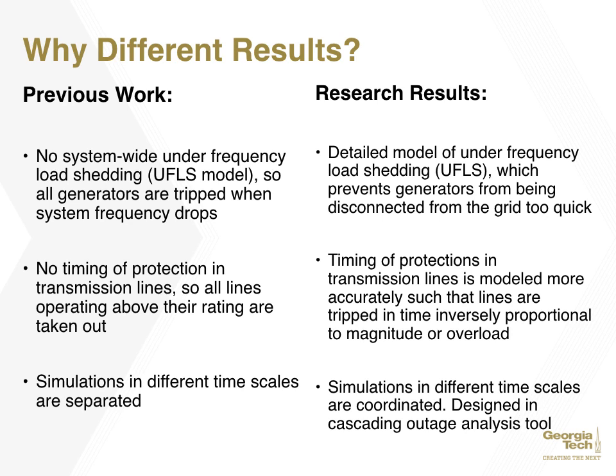In this research, a detailed model of under-frequency load shedding is utilized to prevent generators from being disconnected from the grid too quickly. The timing of protections in transmission lines is modeled more accurately, so that lines are tripped at a time inversely proportional to the magnitude of overload. Conversely, simulations in different timescales are coordinated, designed in a cascading outage analysis tool.